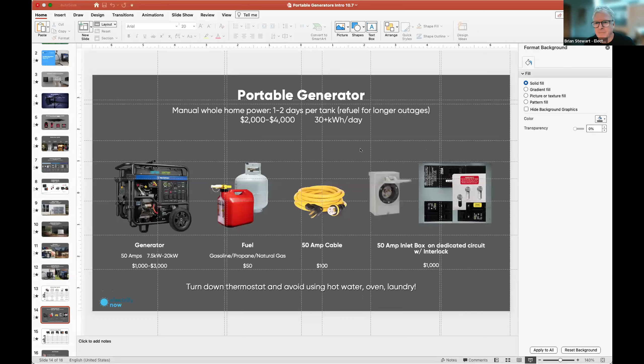The most important thing is to identify how much power you need. In general, if you have high efficiency electric appliances like a heat pump water heater or a heat pump dryer, and also LED lighting, which is very helpful for cutting the power a house needs, you'll be able to get away with a smaller generator, nominally a 30 amp or about 7,000 watts of output.